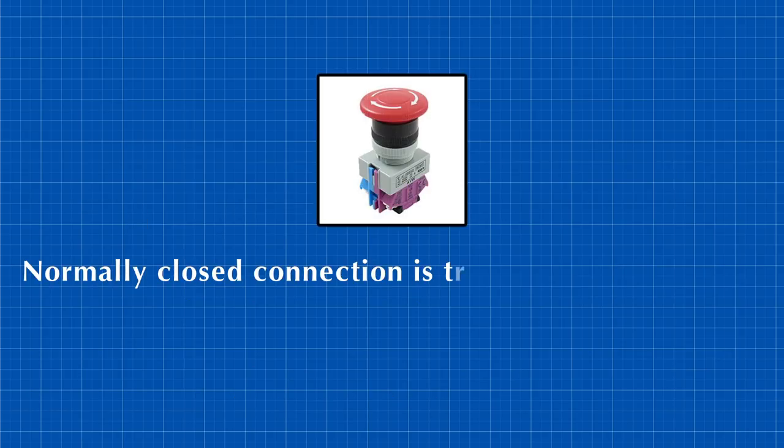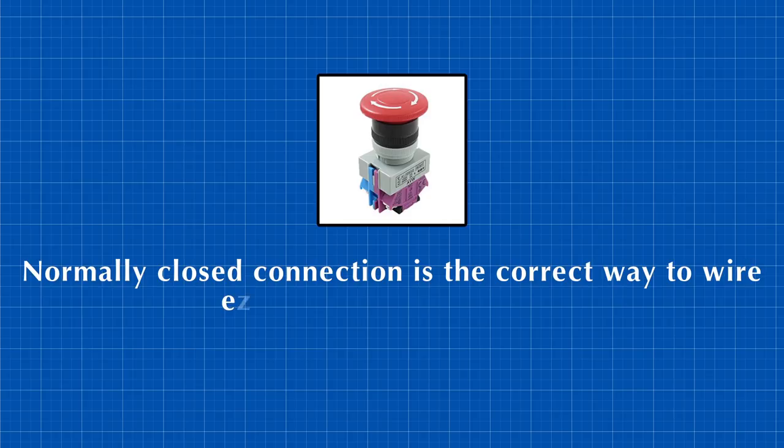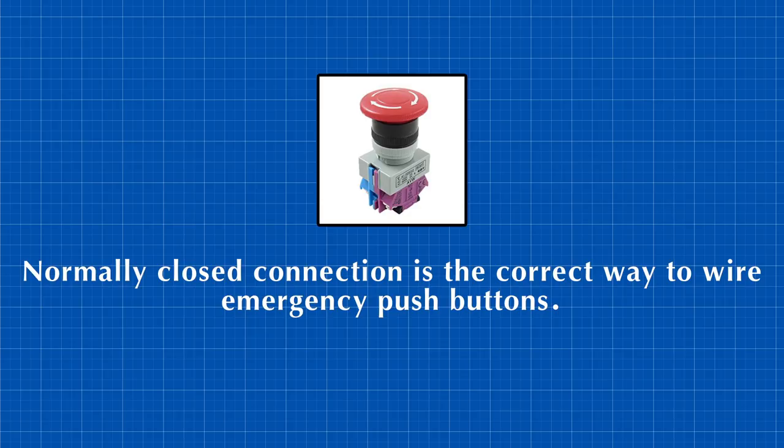This means that using normally closed contact is the correct way because the moment a cut or loose connection happens, the signal will be lost and the control system will sense that and consider it to be an emergency.